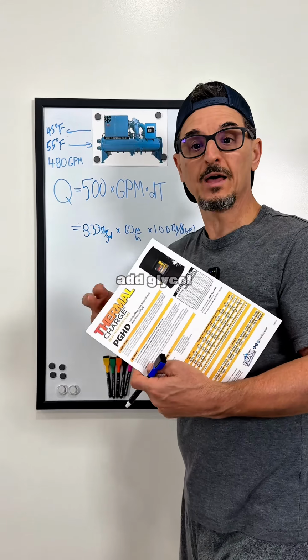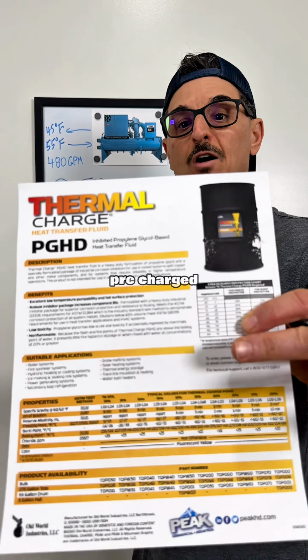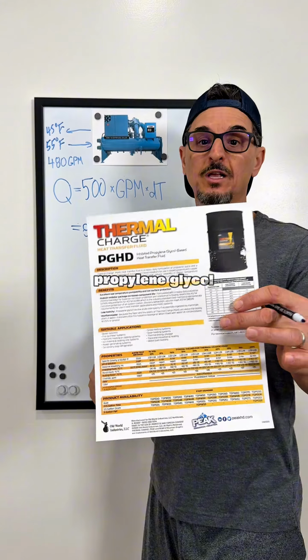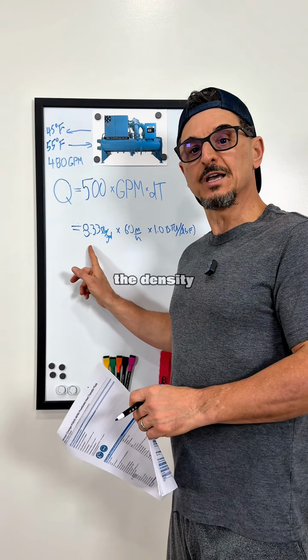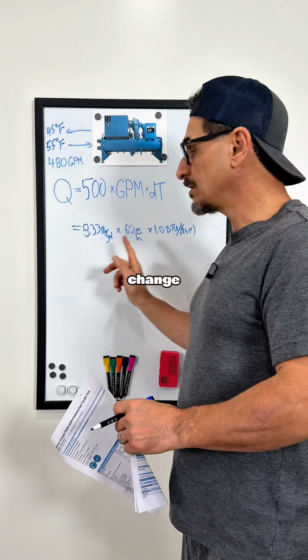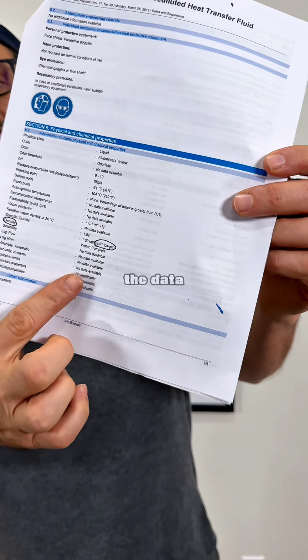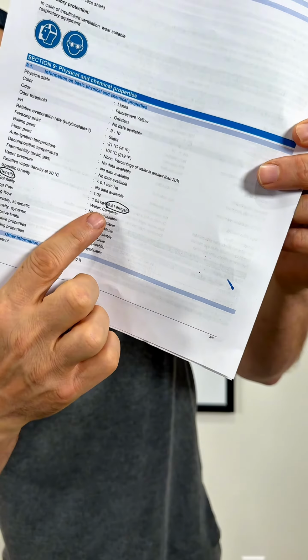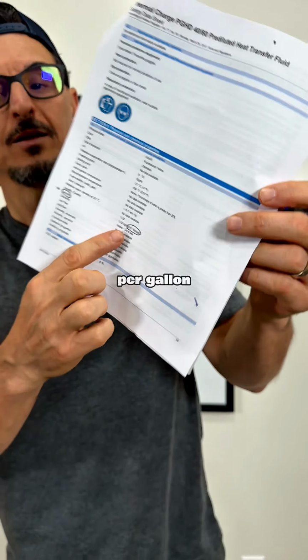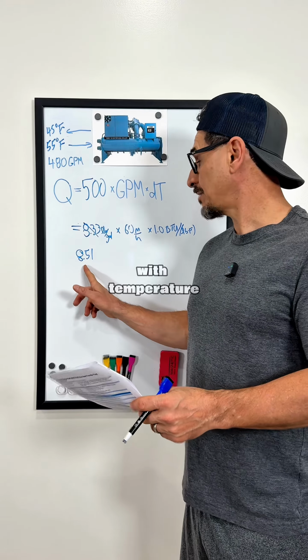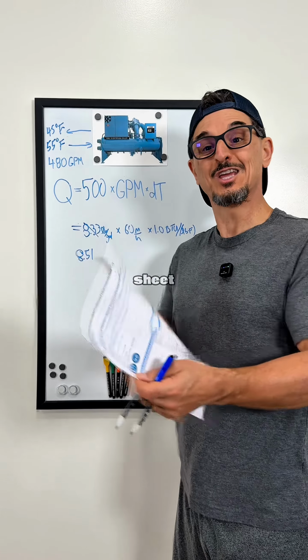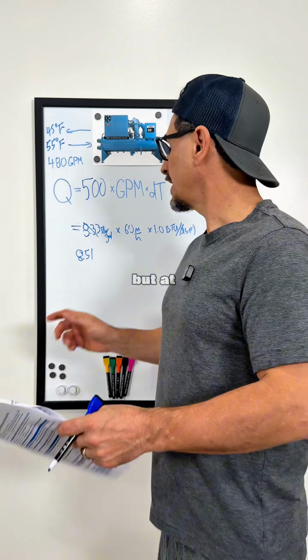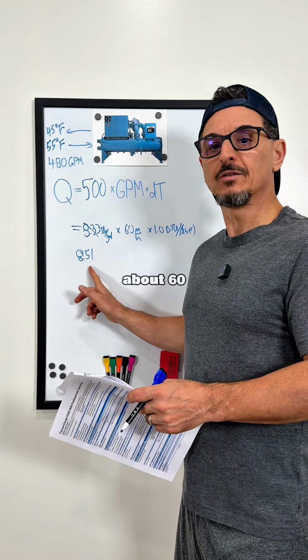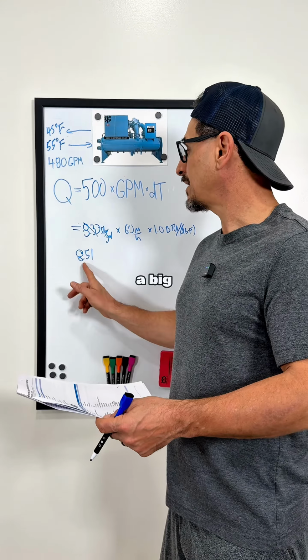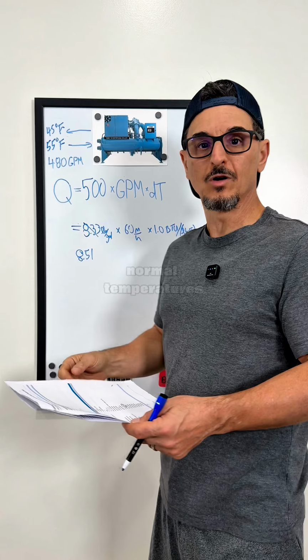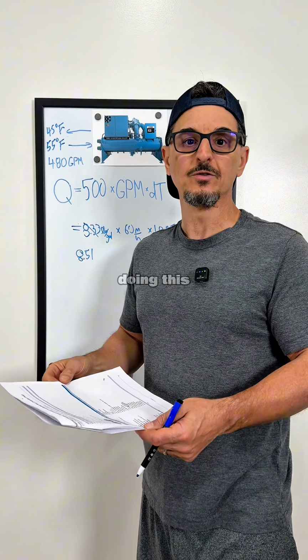So what happens when we add glycol to the system? We've got this pre-charged, pre-mixed 40% propylene glycol solution, and what's going to happen is the density and the specific heat are going to change. So the new density is on the data sheet provided by the manufacturer, which is 8.51 pounds per gallon. Now it's important to note this will change with temperature. I don't see a temperature rating on this sheet. I'm probably just missing it, but at standard, these are rated at about 60 degrees fluid temperature. So not a big deal for this example since we're at relatively normal temperatures, but just be aware of that if you're doing this calculation.